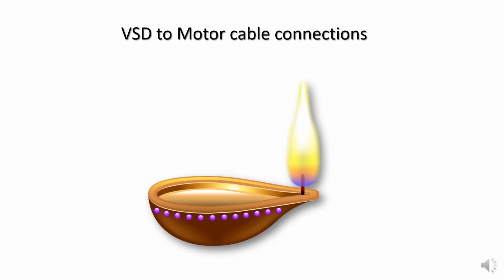In the last few sessions we have already discussed the effect of capacitive current generated by the VSD application for the motor, especially for long run cables. In continuation with this, when we are commissioning a variable speed drive with a motor with especially a long run cable, a distance of 200, 300, 400 plus meters, how can we avoid this capacitive current? That is the topic we need to discuss today in this small session.